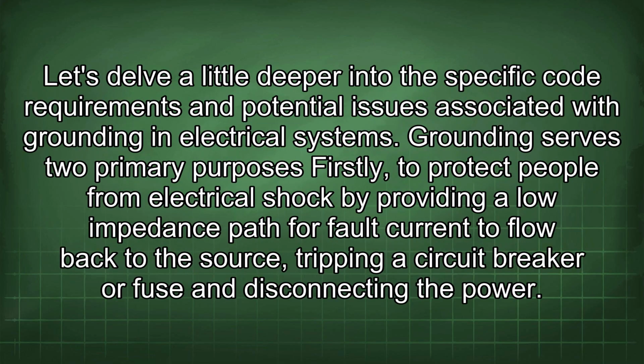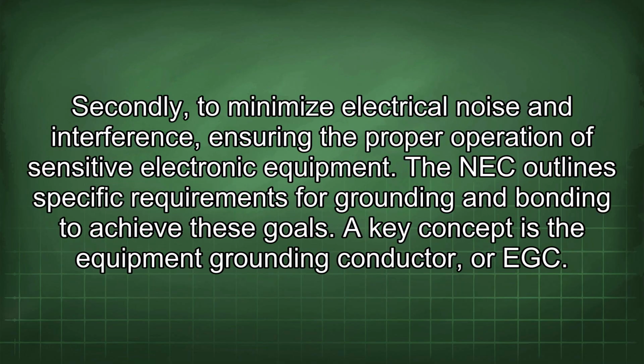Let's delve a little deeper into the specific code requirements and potential issues associated with grounding in an electrical system. Grounding serves two primary purposes. Firstly, to protect people from electrical shock by providing a low impedance path for fault current to flow back to the source, tripping a circuit breaker or fuse and disconnecting the power. Secondly, to minimize electrical noise and interference, ensuring the proper operation of sensitive electronic equipment. The NEC outlines specific requirements for grounding and bonding to achieve these goals.